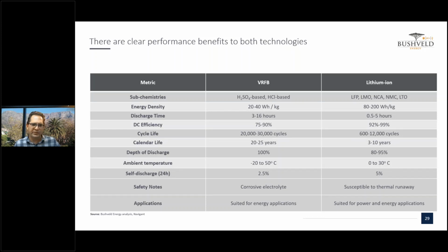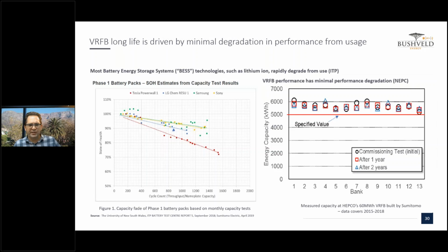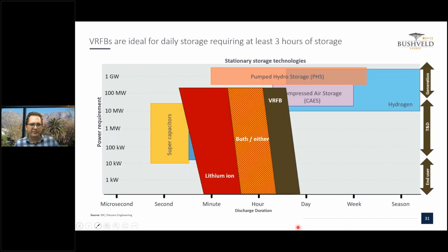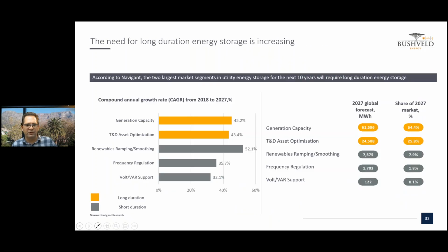I won't go too much into the performance benefits, but these slides show the degradation of lithium versus the measured degradation of vanadium. You can see when they measure it, it goes up and down — it's actually not degrading, that's more to do with temperature effects at the time of measurement. This is from the Sumitomo battery in Japan, and in the long term the electrolyte isn't degrading. So really, where we see VRFBs playing is in that long duration space — looking at this graph, from the 4-hour to say 16-hour storage requirement range, right up to the 100 megawatt level and beyond. That's VRFB's sweet spot in terms of performance.